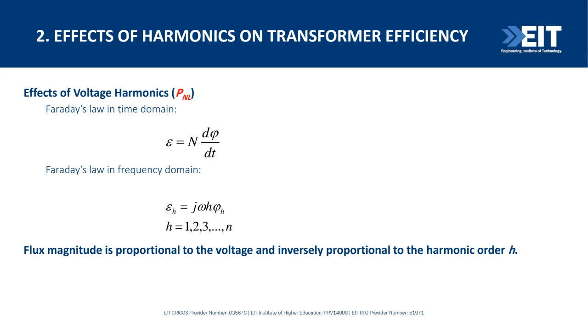So basically, when we have an AC current applied to a primary winding of a transformer, it actually generates a magnetic field in the core, which induces voltage in the secondary winding. According to Faraday's law, when a conductor surrounds a time-varying magnetic field in the core, it can induce a voltage onto the conductor. This induced voltage consequently will result in an AC current flowing through the secondary winding conductors. It can be shown that the induced voltage is given by this expression: epsilon is the induced voltage, which equals N times d phi over dt. And in the frequency domain, we can write it as epsilon_h equals j omega_h phi_h, for h from 1 to n. We do have losses owing to the currents, the effect of current harmonics, actually.